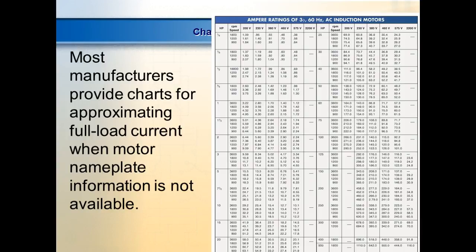A lot of times when they rebuild them, they'll paint them. If the nameplate is not embossed, and it's just painted on there, then they cover up every bit of it and you can't read it anymore. Try to scrape off the paint, and you scrape off all of it. On a new motor, you're exactly right, it's going to be on there. But this one right here is nothing but a sticker. It's not embossed, it's not metal.